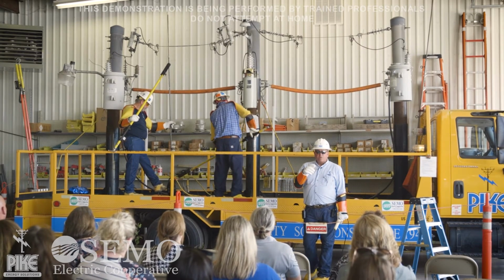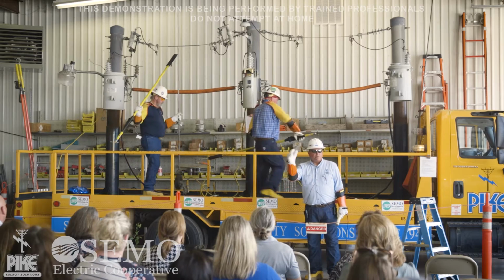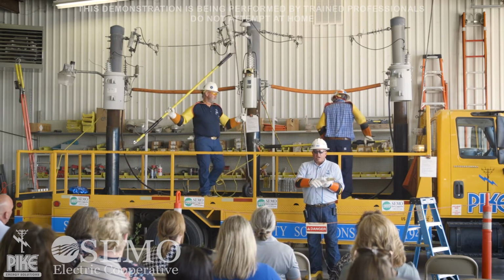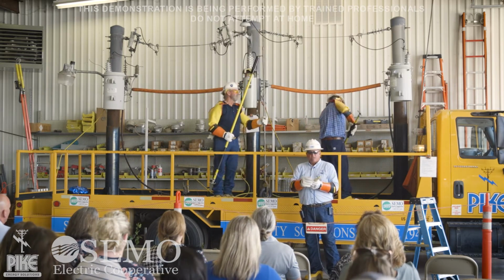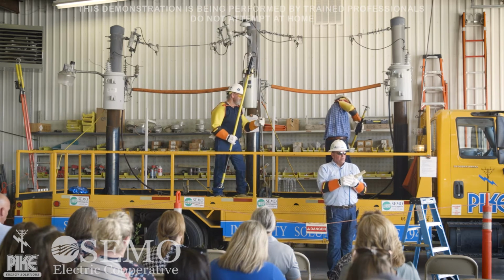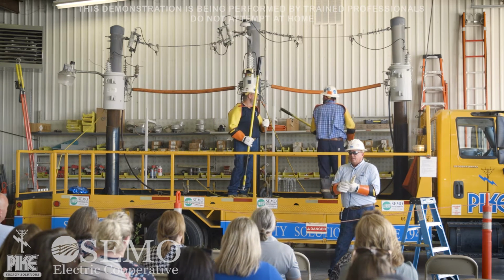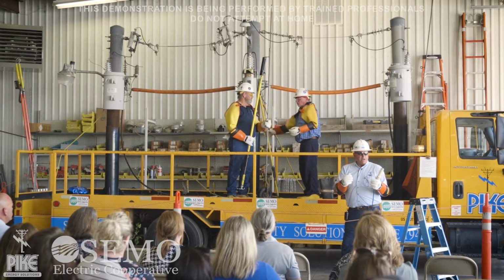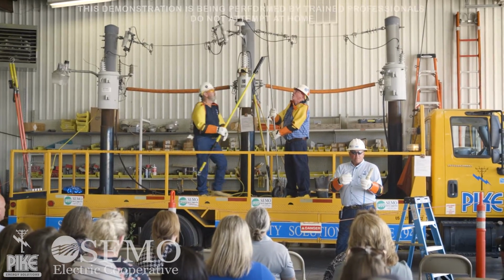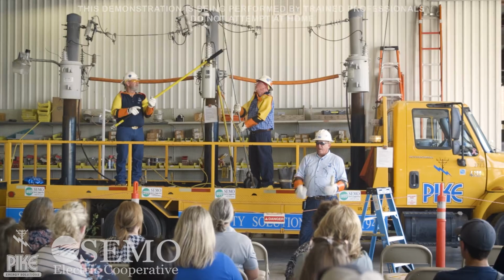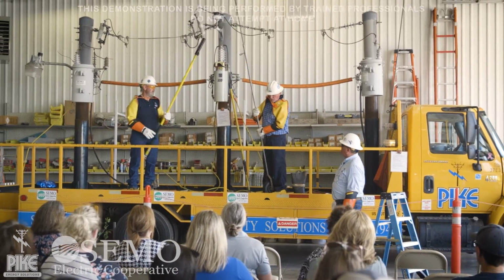But think about how those grounds are installed — I'm talking to the lineman now. We've got to make sure that surface contact is clean, those grounds are in good condition, and that connection is as tight as we can get it, because we're trying to stop that energy. Now, it's not going to stop all of it — there's still going to be a little bit that gets past it, depending on how tight those grounds are.